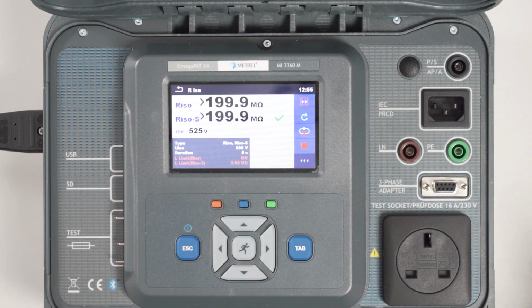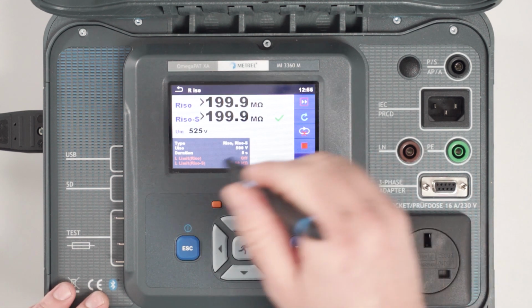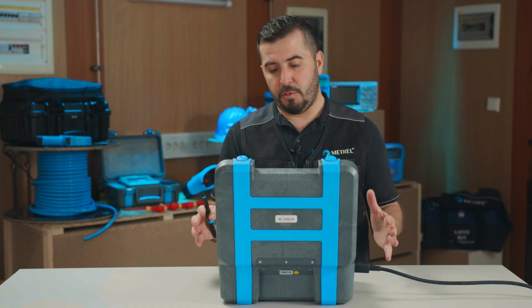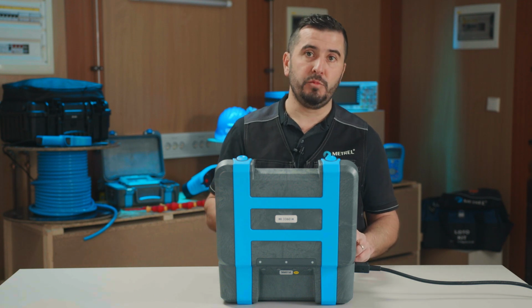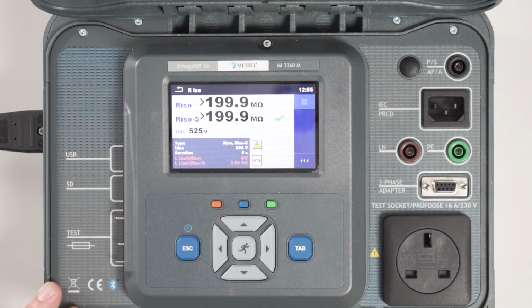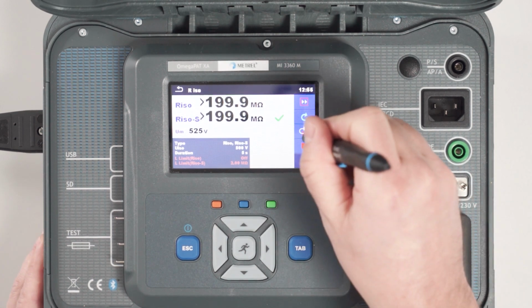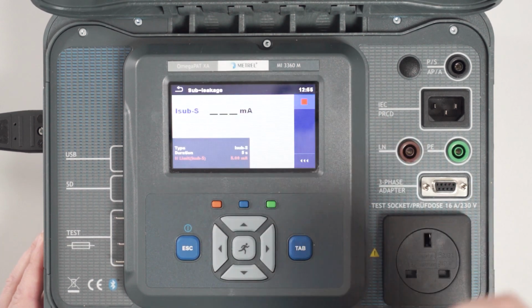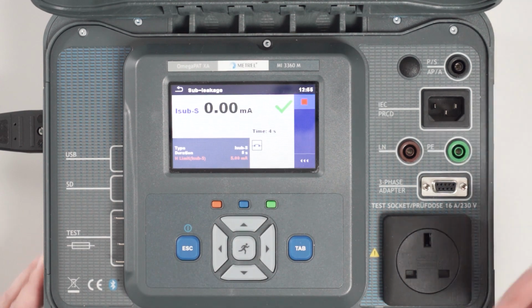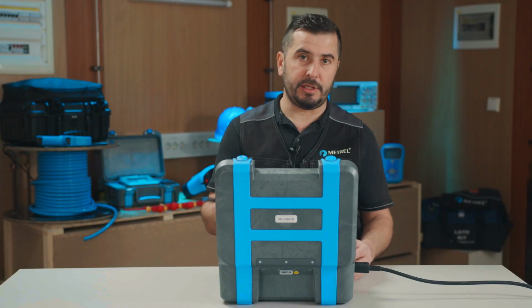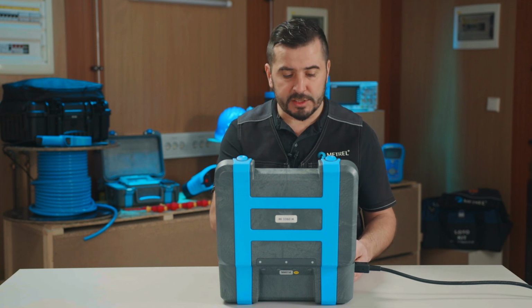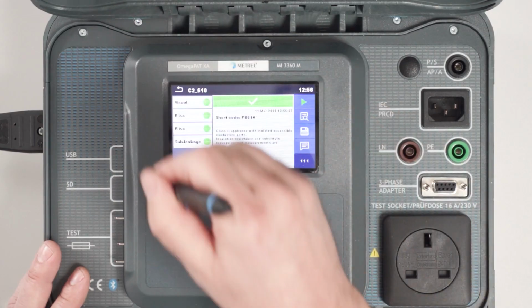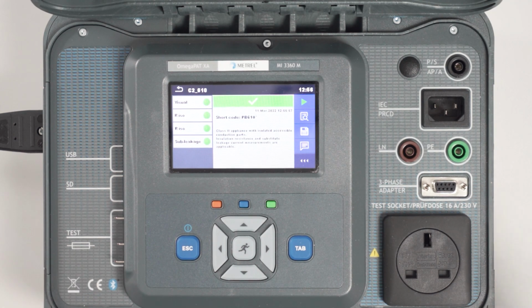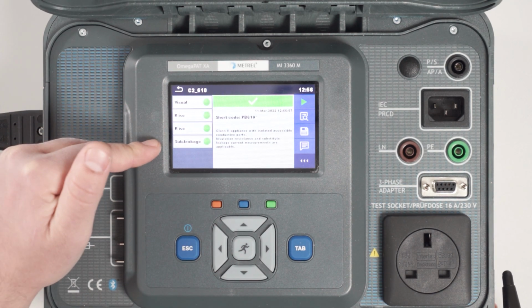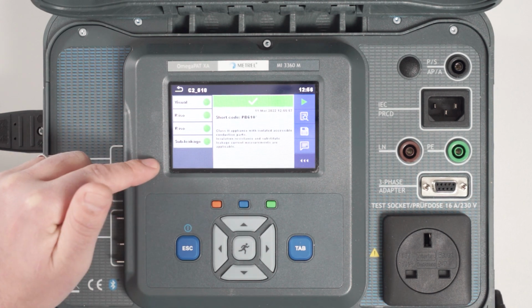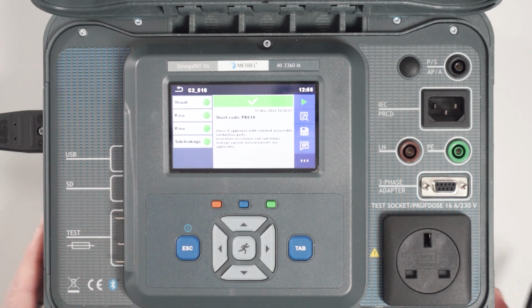We can now finish this first step of our insulation resistance, and we can make another one. Why can we repeat it? Because we selected multiple points testing. So we finish the second step, and we can now end the loop, which means that the instrument will proceed with the next step, in our case the substitute leakage with the probe. After all these tests are finished, we see that we have two insulation resistance test results, the substitute leakage, and the result of our visual inspection.